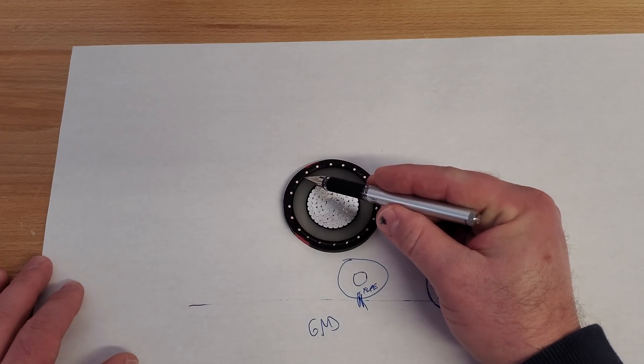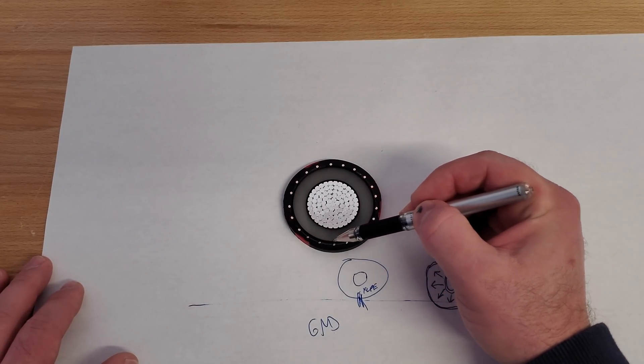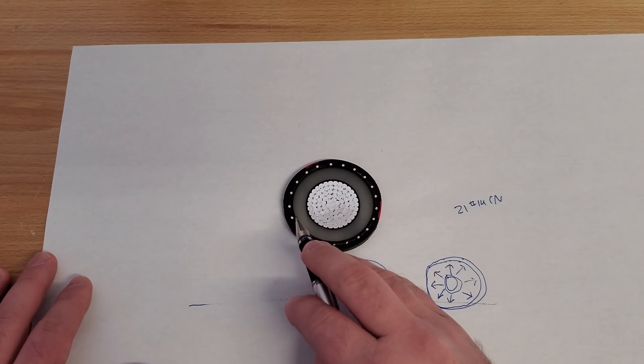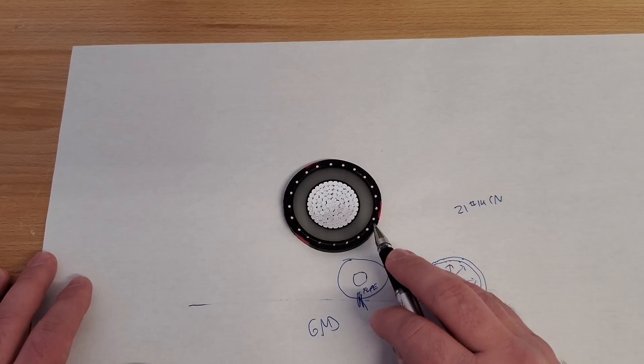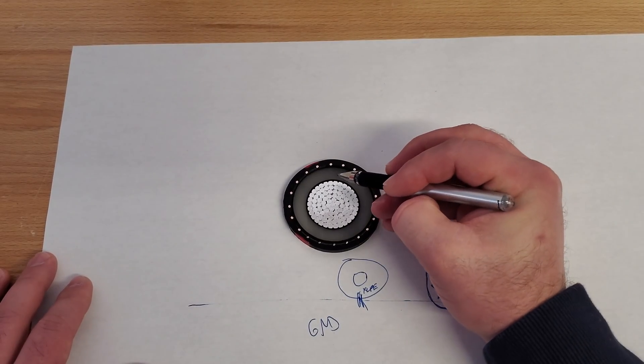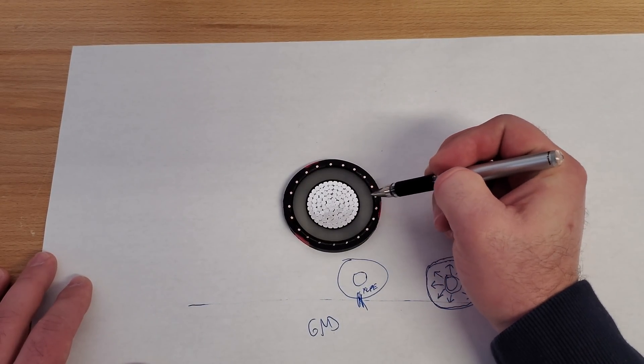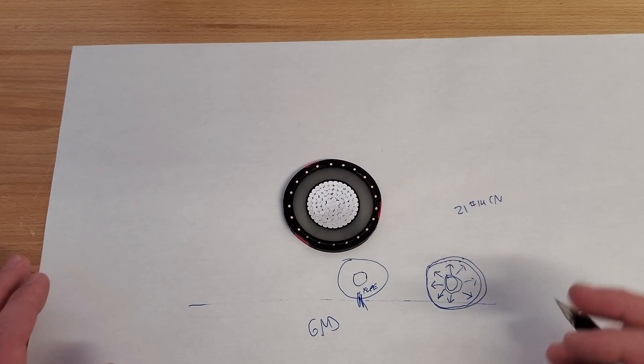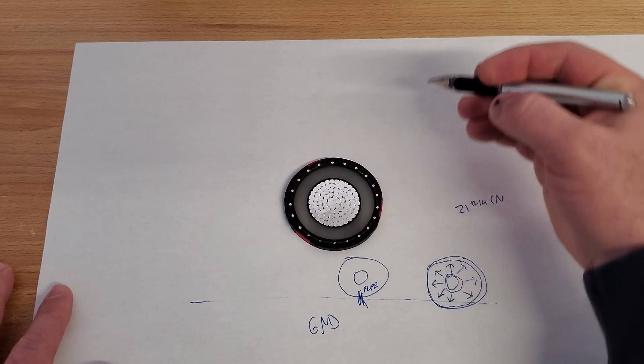So very important that this layer basically keeps this insulation shield grounded. Again, it's evenly distributed around that semi-con layer. So as the lines of flux bleed through the insulation evenly, they're ultimately bleeding to these concentric neutrals, which at the terminations on either side are grounded. So this is the actual grounded layer.